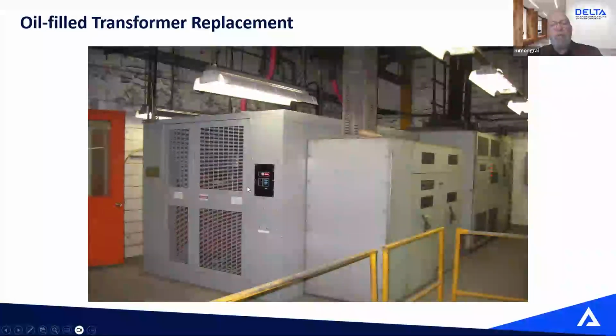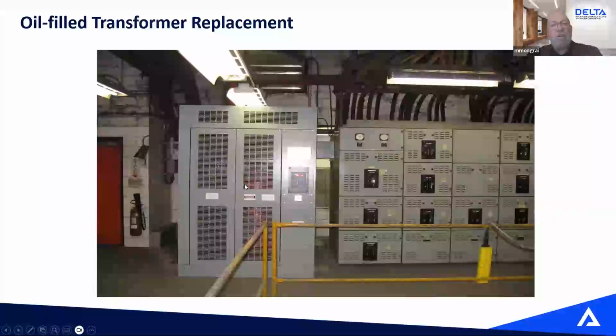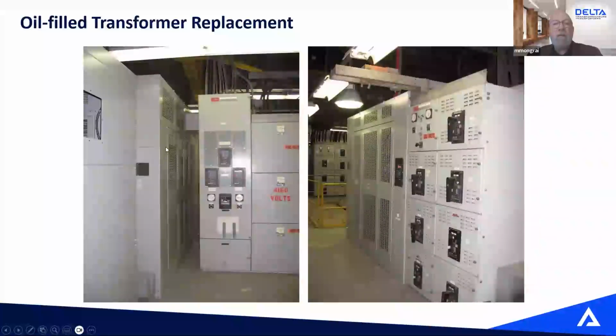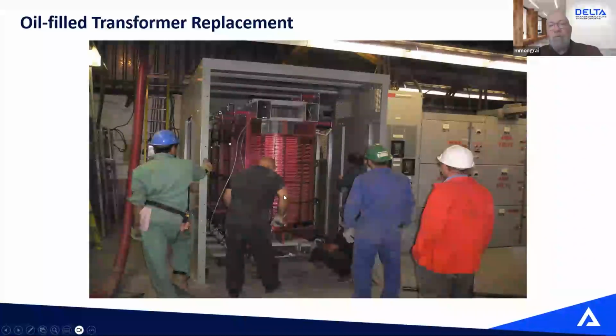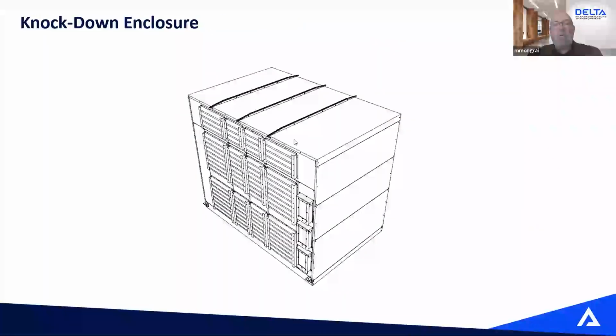So everything is custom built for those solutions, custom enclosure, custom core and coil. So that's the front of your transformer, which usually is going to be your right side, and you have flanges on the side like this. And you see here, the front of the transformer is here, and you see the buswork goes there. And of course, it's a big job to move those transformers in place. But if it's well planned, well executed with the right measurements done up front, 99% of the time the job can be done, and there's not a piece of steel that needs to be cut or redrilled, because it was executed properly and the measurements were done the right way, if I could say.